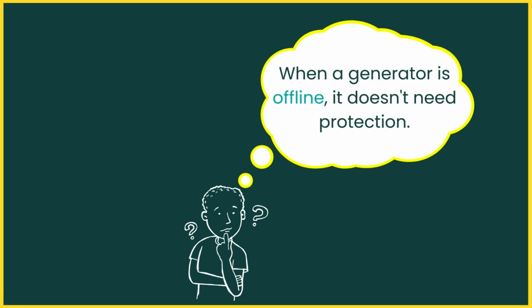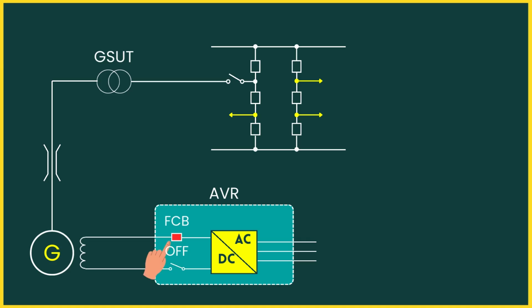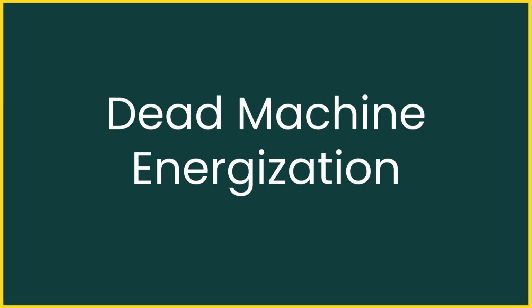Many engineers think that when a generator is offline, it does not need protection. After all, there is no excitation, no grid connection, and seemingly no risk, right? But that is not true. An offline generator can still be inadvertently energized, a condition also known as dead machine energization. And if that happens, serious damage can occur within seconds.